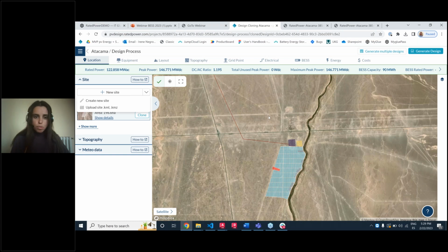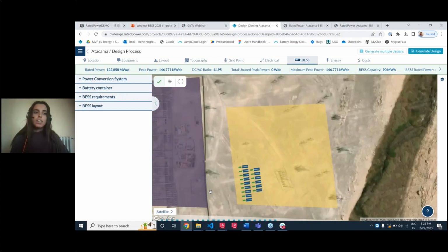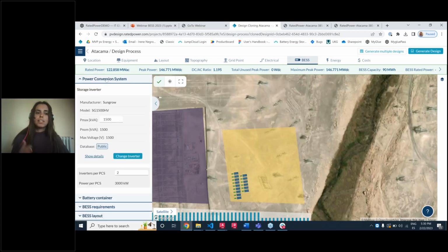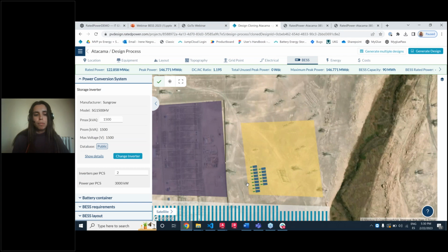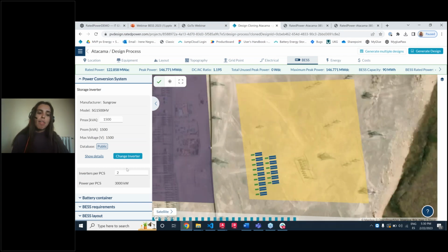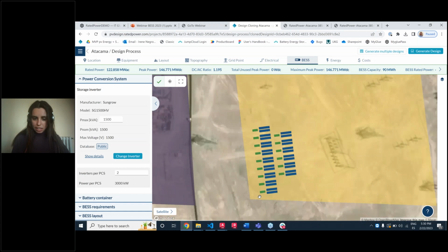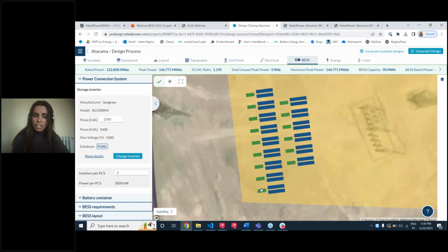Let's go to the next question: how did you define the size of the battery? Let me go back to the battery energy storage system tab. First you have to define the power of the PCS, or the power conversion system, by selecting the storage inverter you would like to consider and the number of inverters per PCS. For example, in this specific case we selected a 3 megawatt PCS, shown in this square here.